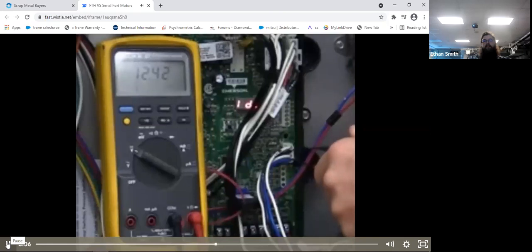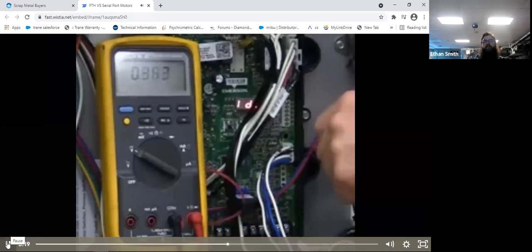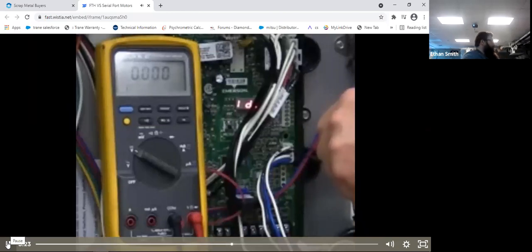If I do not have the 12 volt source voltage, I know that my control board is at fault and I need to replace the control board. The next element I'm going to check is my transmit ground. Now this is the individual packets that the motor is sending. So transmit on my control board is going to move to receive on my motor.